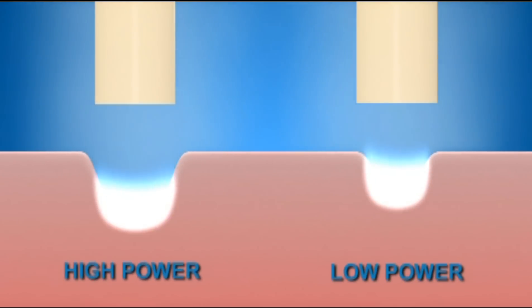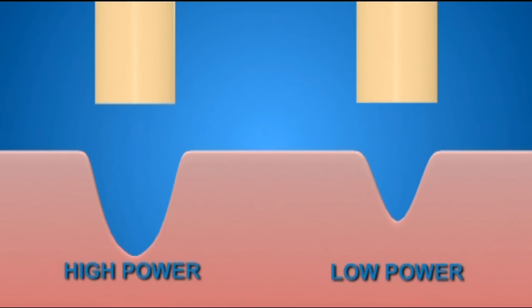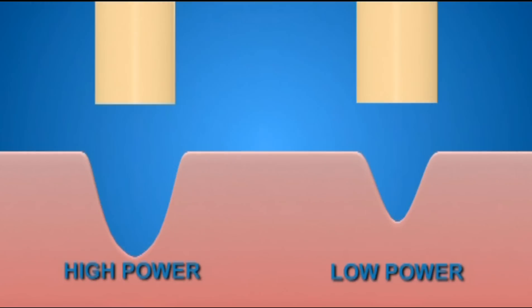Let's start with power. These buttons increase or decrease the amount of laser energy coming from the tip. Higher power makes a deeper, slightly wider cut. Use higher power for more fibrous tissue. As you cut, adjust the power for the results you want.